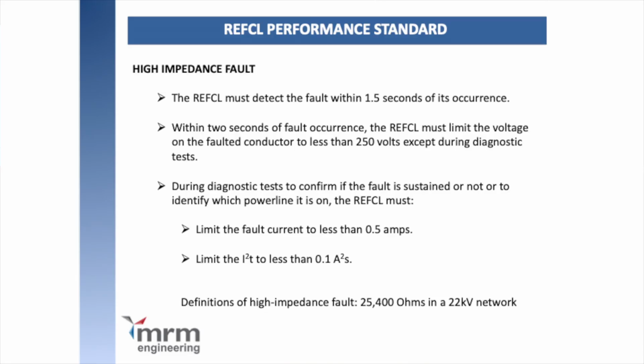High impedance fault. So the REFCL must detect the fault within 1.5 seconds. Within 2 seconds, it must be down to 250 volts. During the tests, to confirm the fault is sustained, not to identify which power line. So they did the test, they come up with less fault current than 0.5 of an amp, and the I squared T, which is the energy that causes the ignition, must be less than 0.1 amp squared seconds.